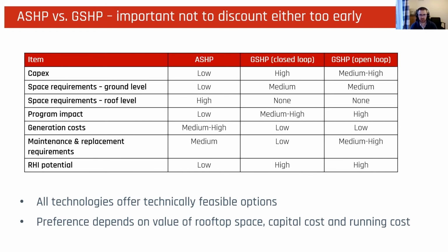From a generation cost perspective, I think ground source is likely to lead the way because of its lower dependency on ambient conditions. Air source at the moment, you know, that sensitivity with its poor performance when it's at -3, -5 degrees outside is going to push the running cost of air source heat pumps compared to ground source heat pumps up. But I think the use of thermal storage and innovative control systems that decouple site demand from generation timing should bring that down, and something we need the industry to bring through.